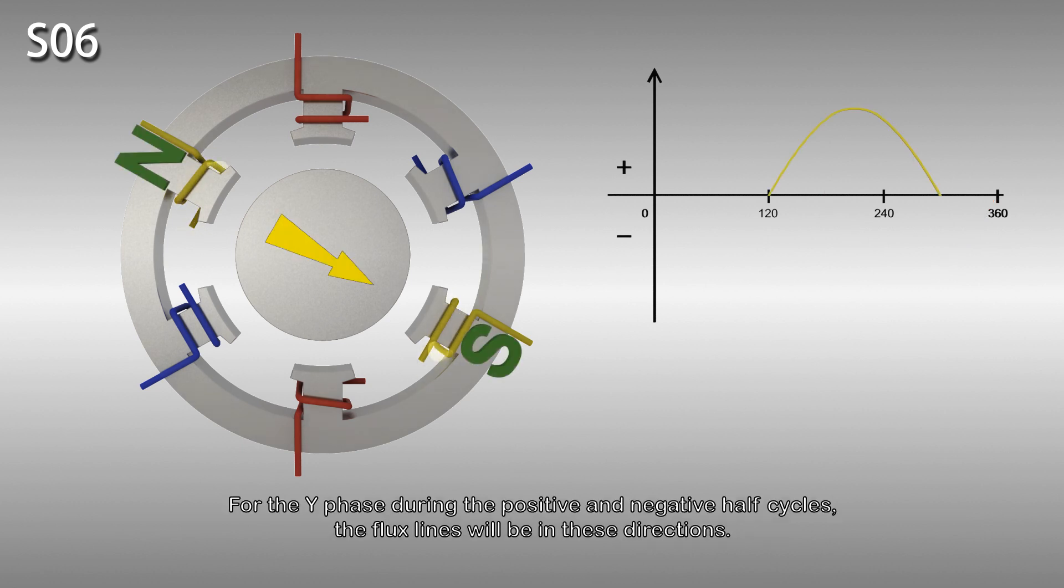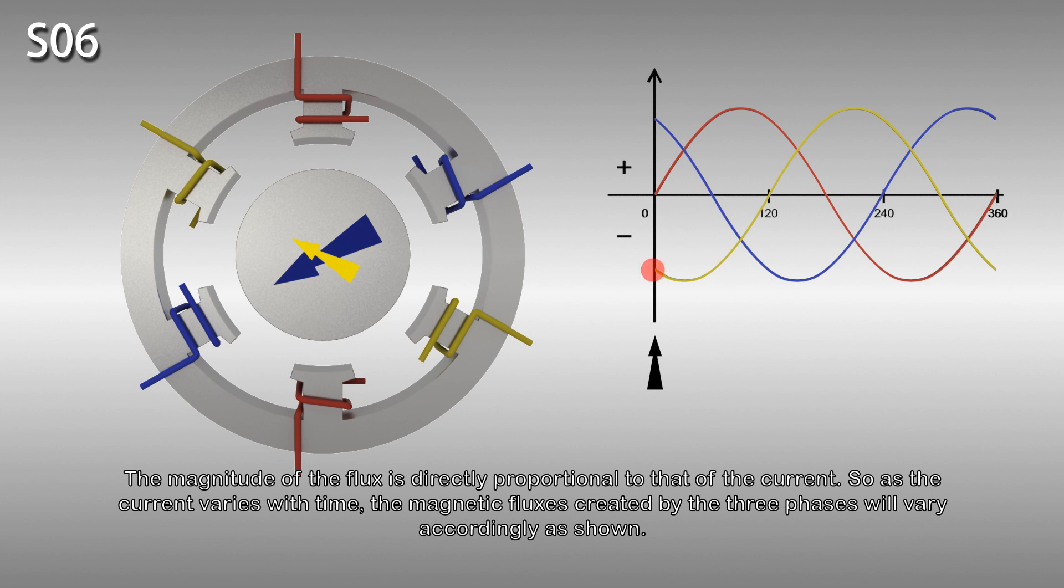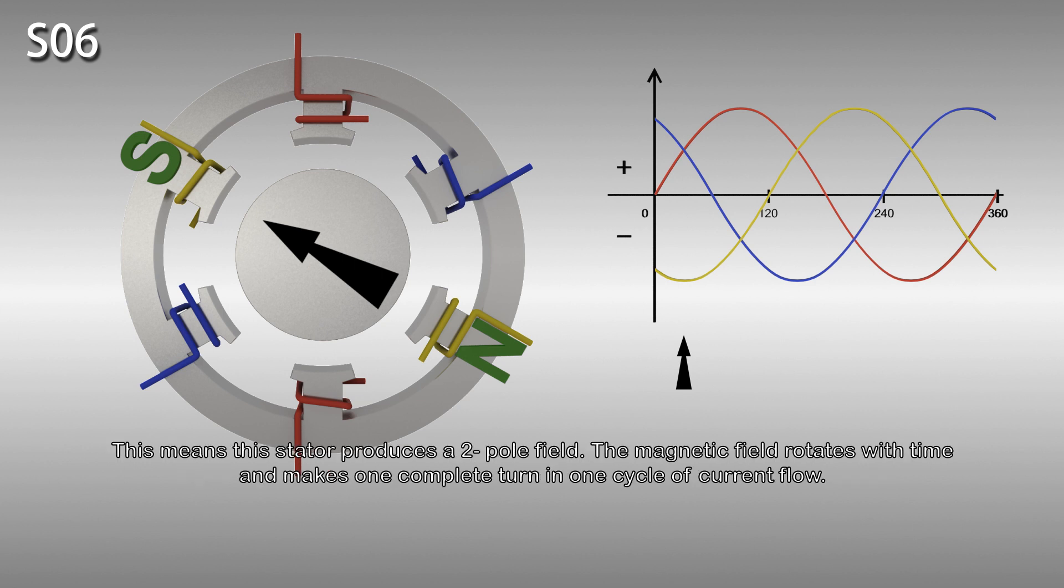For the Y phase during the positive and negative half cycles, the flux lines will be in these directions. For the B phase during the positive and negative half cycles, the flux lines will be in these directions. The magnitude of the flux is directly proportional to that of the current. As the current varies with time, the magnetic fluxes created by the three phases will vary accordingly as shown. As flux lines can't cross each other, the three fluxes combine and produce a magnetic field, having essentially one broad north pole and one broad south pole. This means this stator produces a two-pole field.